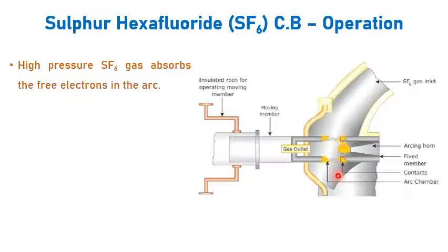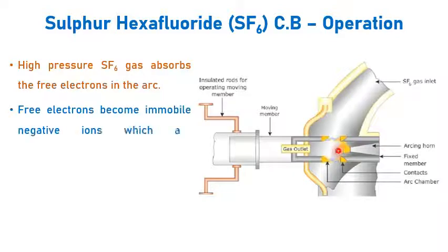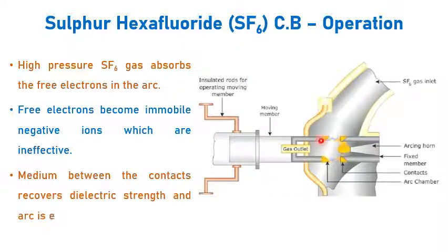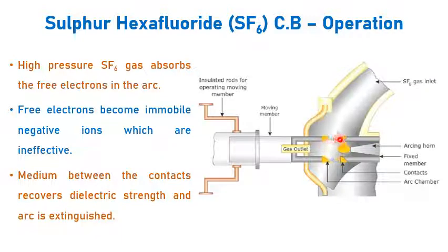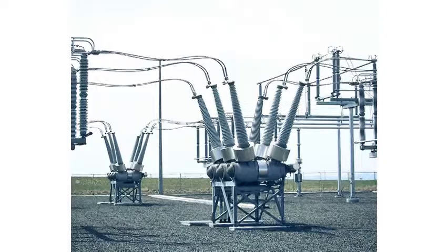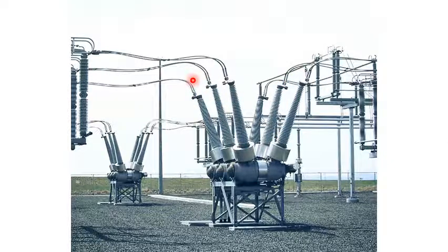This high-pressure SF6 gas absorbs the free electrons present in the arc. The free electrons become immobile negative ions, meaning they cannot move freely, so current cannot flow through the gap between the contacts. The medium between the contacts recovers its dielectric strength at a faster rate — deionization happens and the arc cannot re-strike further. This is how an SF6 circuit breaker in a substation looks, with incoming lines, outgoing lines, and the arc quenching chamber.